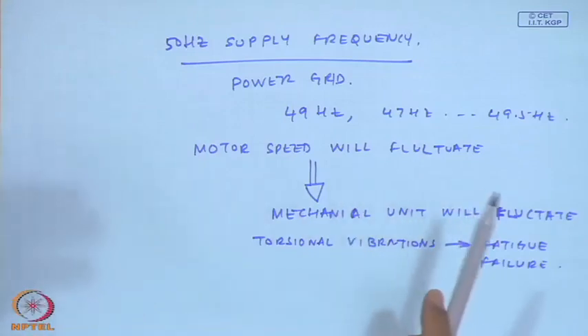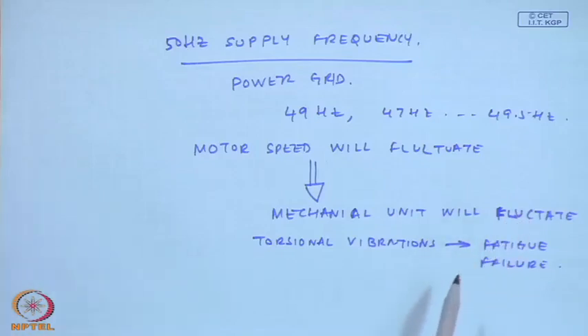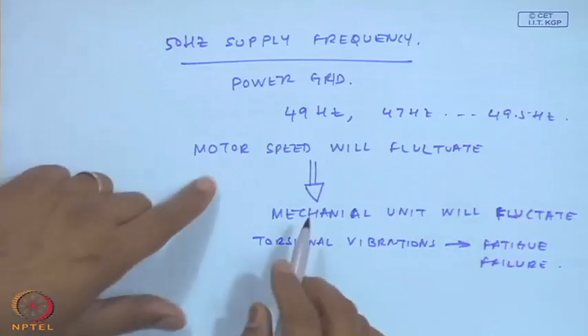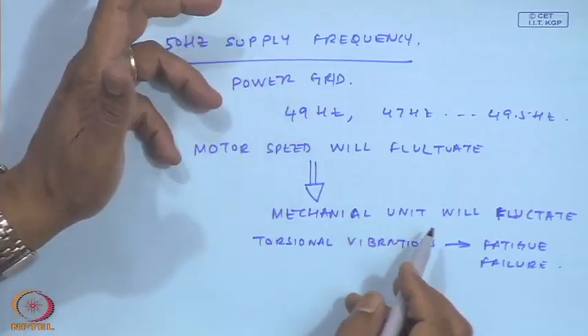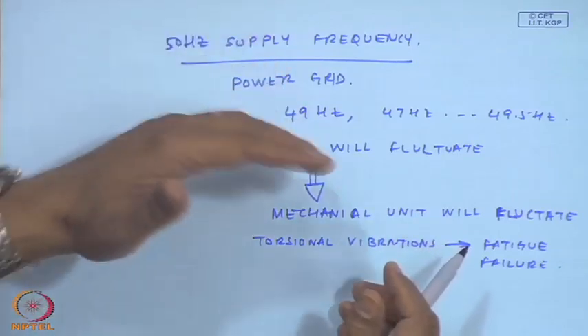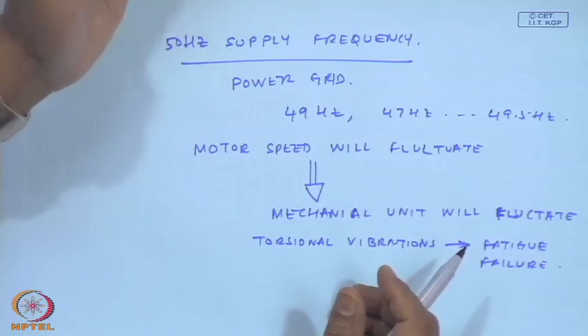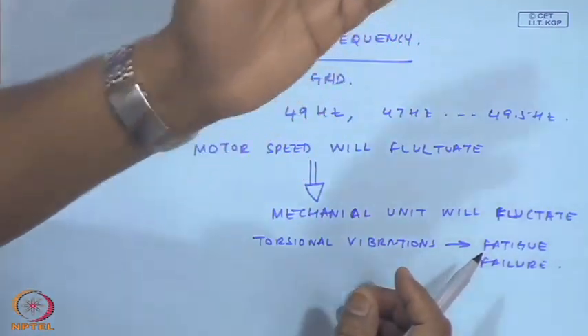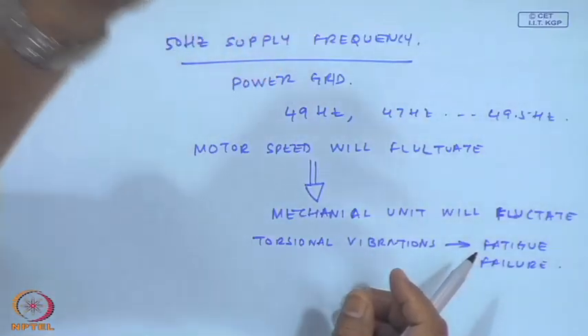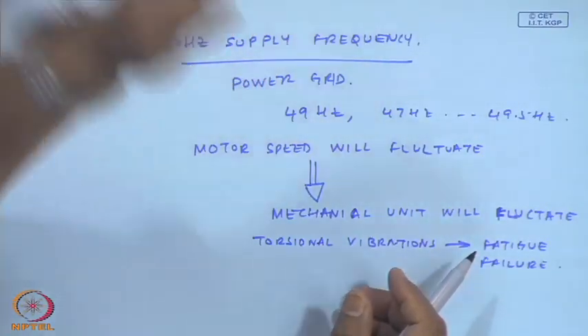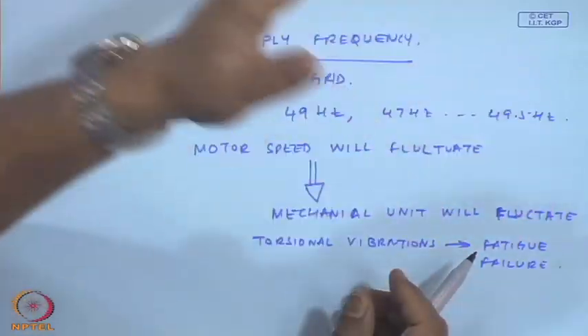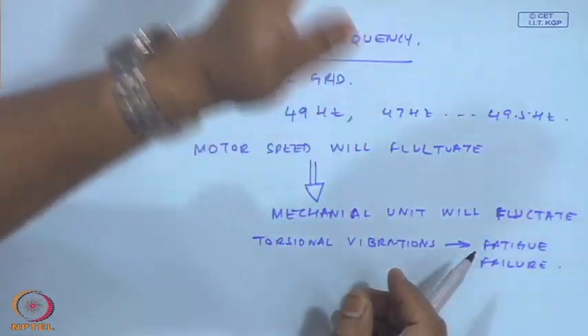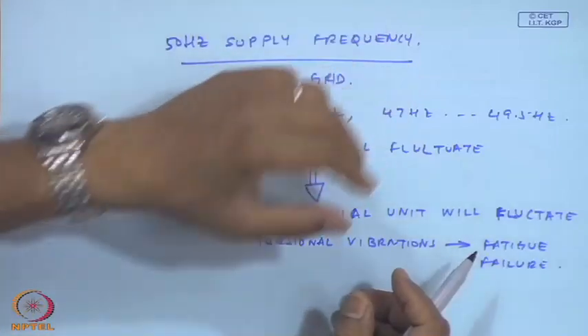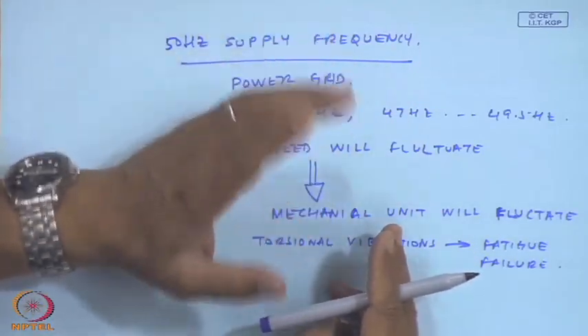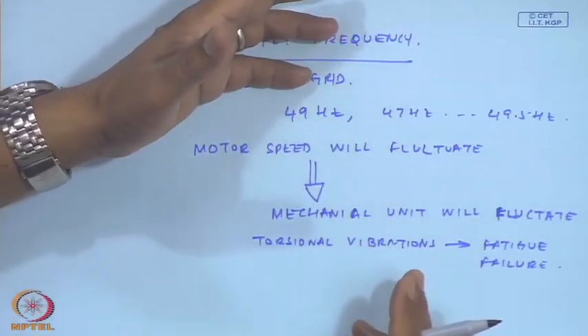Of course, in modern machines there are many safeguards to prevent that. The system itself will trip. You have seen how the grid failure had a domino effect, with grids failing one by one. If the grid fails and you do not take up the load, the speed and frequency are again going to increase. So in a power generation place, they always have to maintain balance between the load and the production rate, and they have to monitor the 50 hertz. If you have ever been to a power plant, you will see they constantly monitor the supply frequency, or the power generation frequency, at 50 hertz.